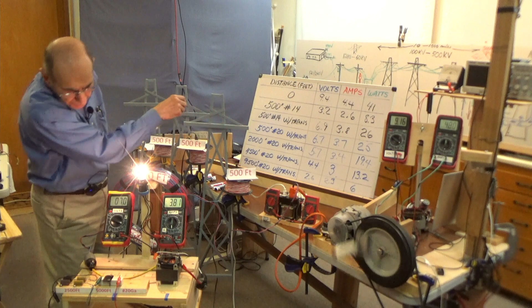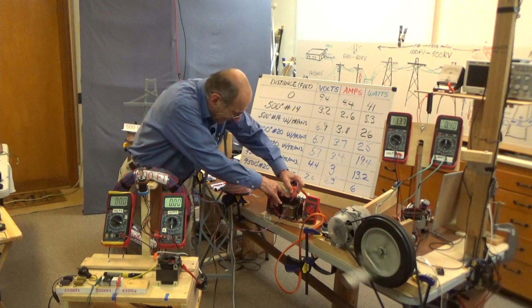7, 7.1, 3.8 - well, I'm doing better than last time. So here's the 500 feet of number 14 with a transformer. I've got 6.9, a little higher, and 3.8. So we're getting a little more than 26 today, but about that amount. Pretty good, huh? See what the transformer did for us already?